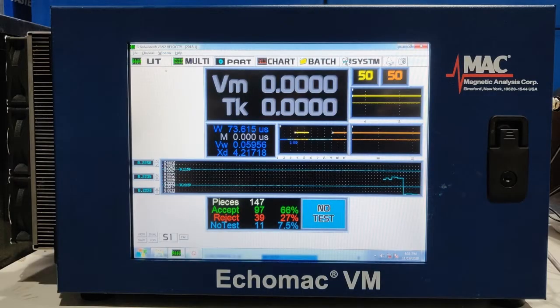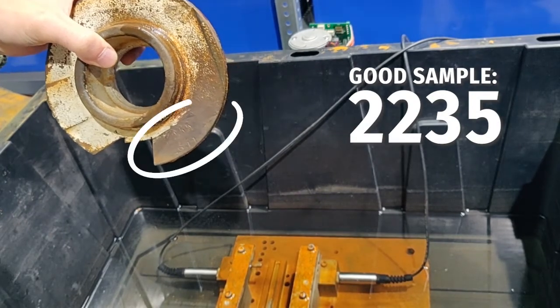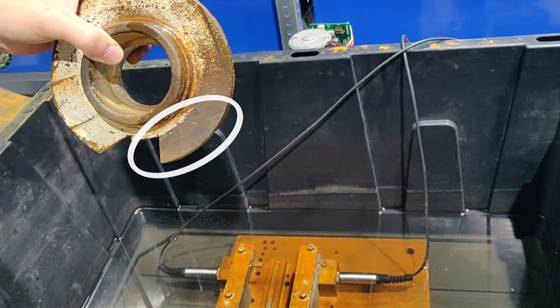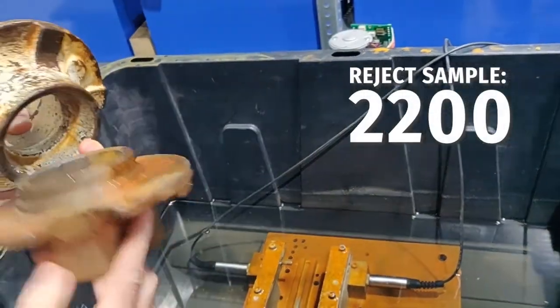This is a demonstration of the basic functions of the Magnetic Analysis Corporation velocity tester. The tester is used to determine nodularity in cast iron, which is correlated to the sound velocity in the material. We will use two customer samples in the demonstration. The good or acceptable part is stamped with its speed of 2235, or .2235 inches per microsecond. The reject shows a speed of 2200.